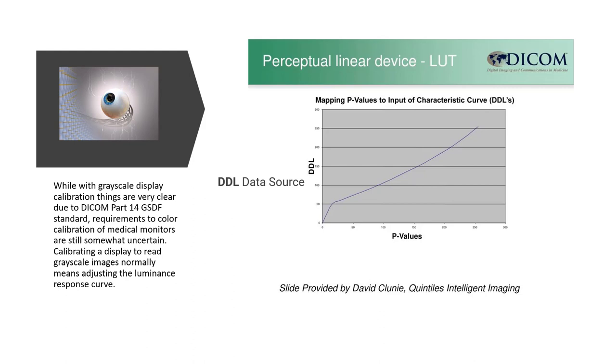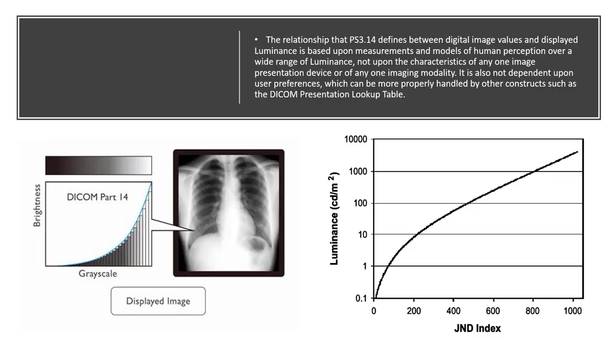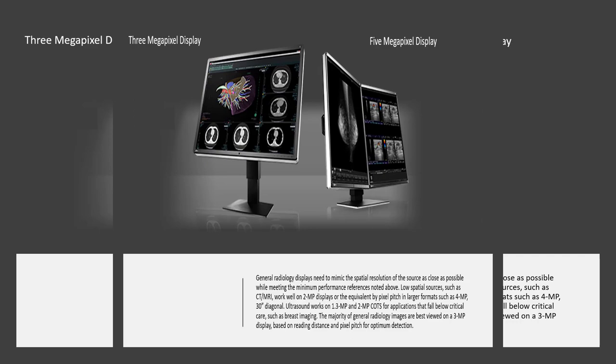Calibrating a display to read grayscale images normally means adjusting the luminance response curve of the monitor to reflect what are called just noticeable differences, or JNDs, which is the differences just noticeable to the human eye, to create P values or presentation values. This monitor shows an image created with P values, which were based upon the just noticeable differences in luminance index that we see to the right. To create the image we map these grayscales based upon lookup tables for the specific image and position.